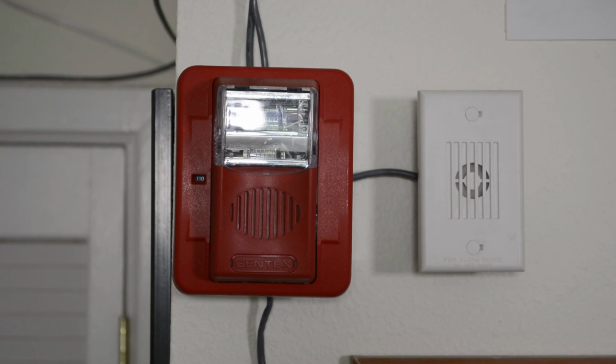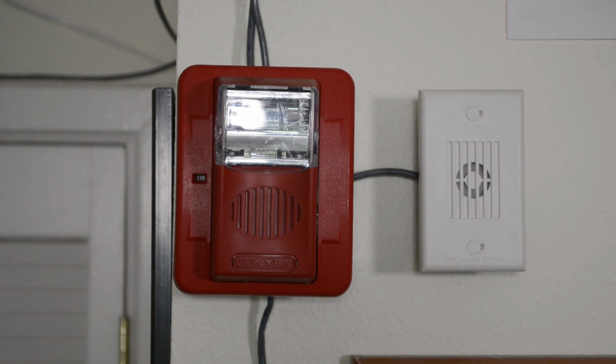Okay, so hopefully this next tone is going to be a little bit more pleasant. We're going to be using the continuous chime, which will chime about once per second, if I do recall correctly. So I've got this set up on continuous, the panel's on continuous, so it's just really going to continually ding once per second. And hopefully this will be a little more pleasant than the 2400 Hertz. Maybe.